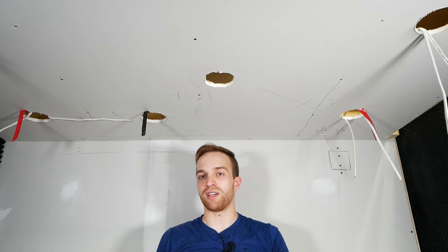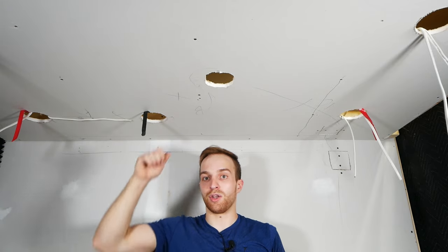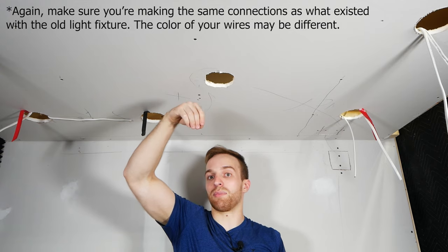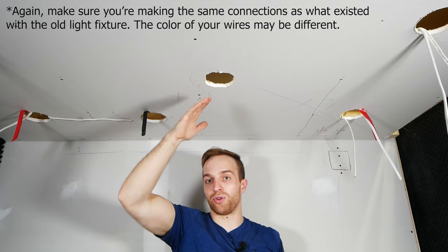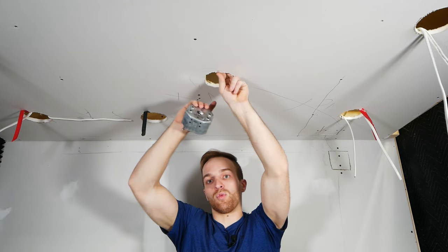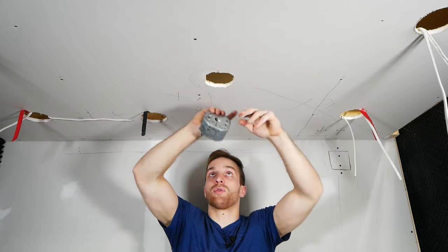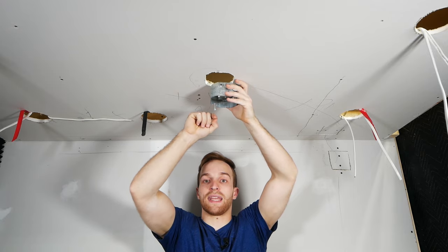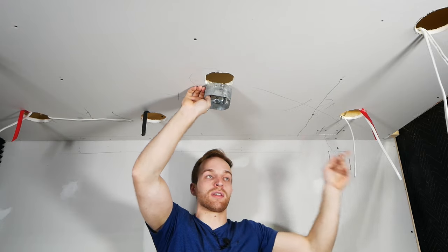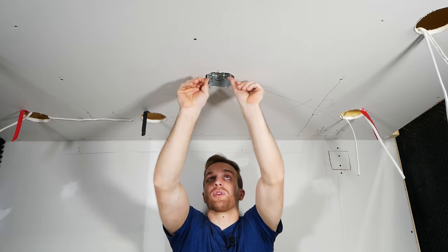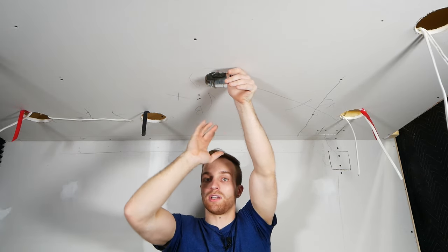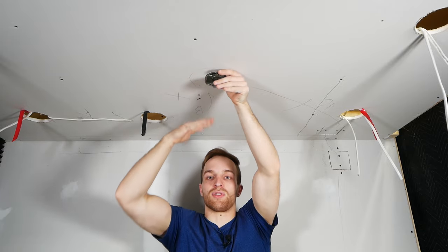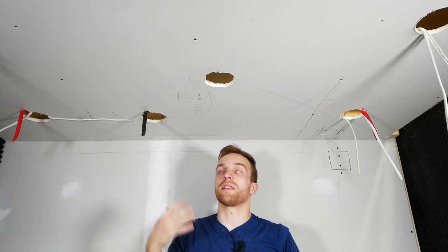So essentially what we're doing is we're taking a wire from here to here and the wire at the octagon box is going to tie into the same wires that were going to your light fixture. So just think of it as if the wire is your new light fixture. You're going to tie the black to the black, the white to the white, ground it with all the other grounds and then that way when you think about turning the switch on, now the power is going from this box, it's going to that connection and then it's leaving out to your pot lights. And then with this box you just throw a blank canopy cover on it and then that way if you ever need to access the junction again it's right there.